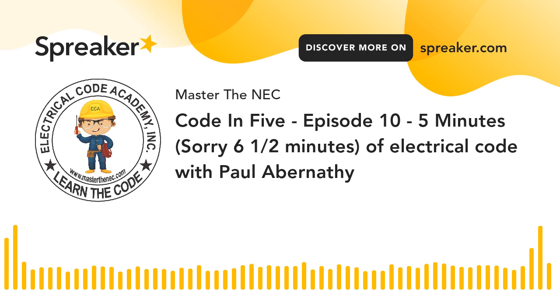Now, number 2 says, okay, what if I still don't know those terminal limitations? Maybe it's an old device. I can't see what the temperature rating is on it, and I can't see what the rating is on the circuit breaker, but I do know that the conductor falls between 14 and 1, or it's 100 amps or less, which seems to tell me that I have to stay in the 60 degree ampacity column of 310.16.